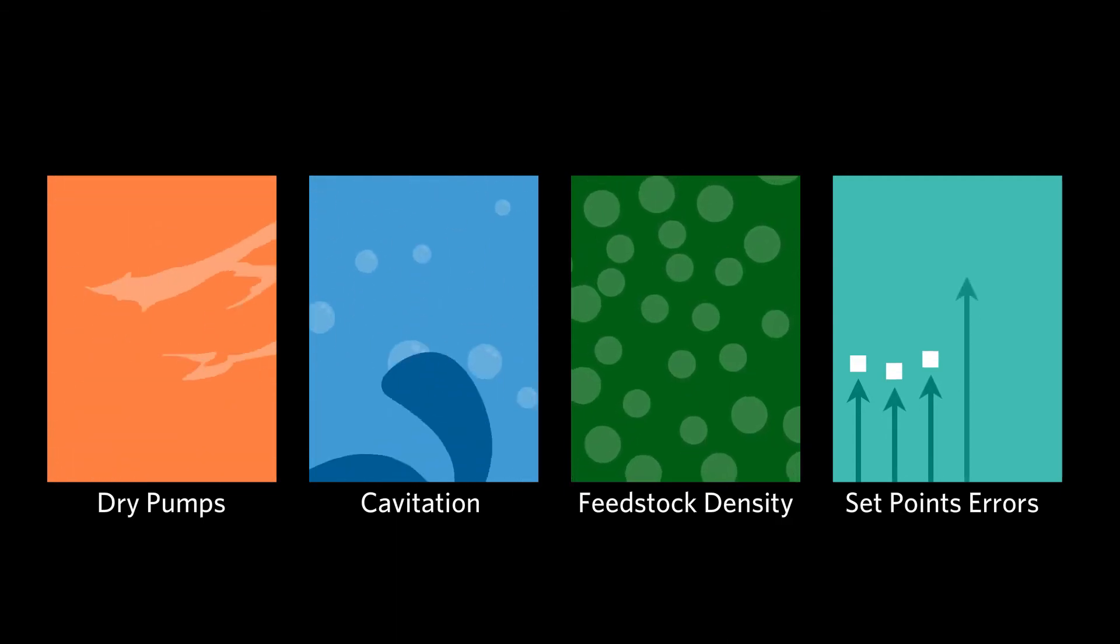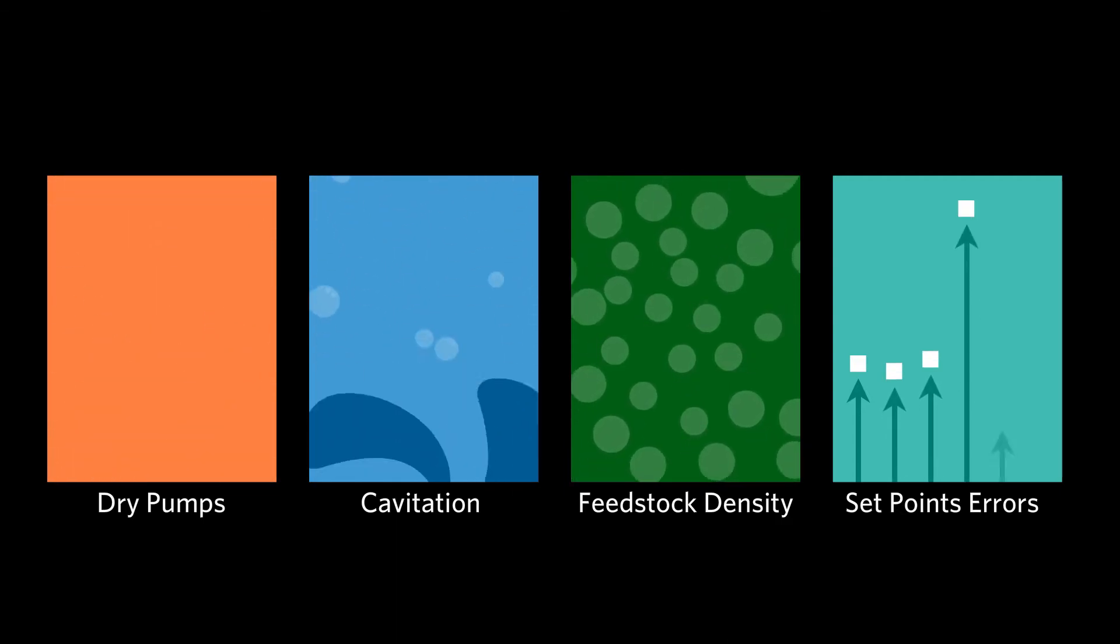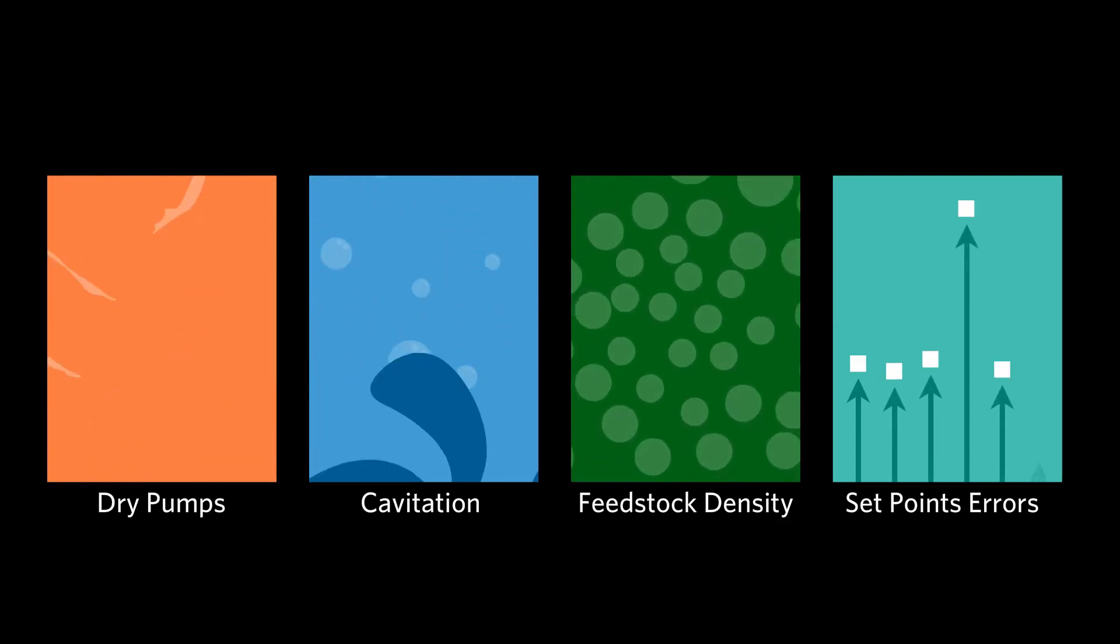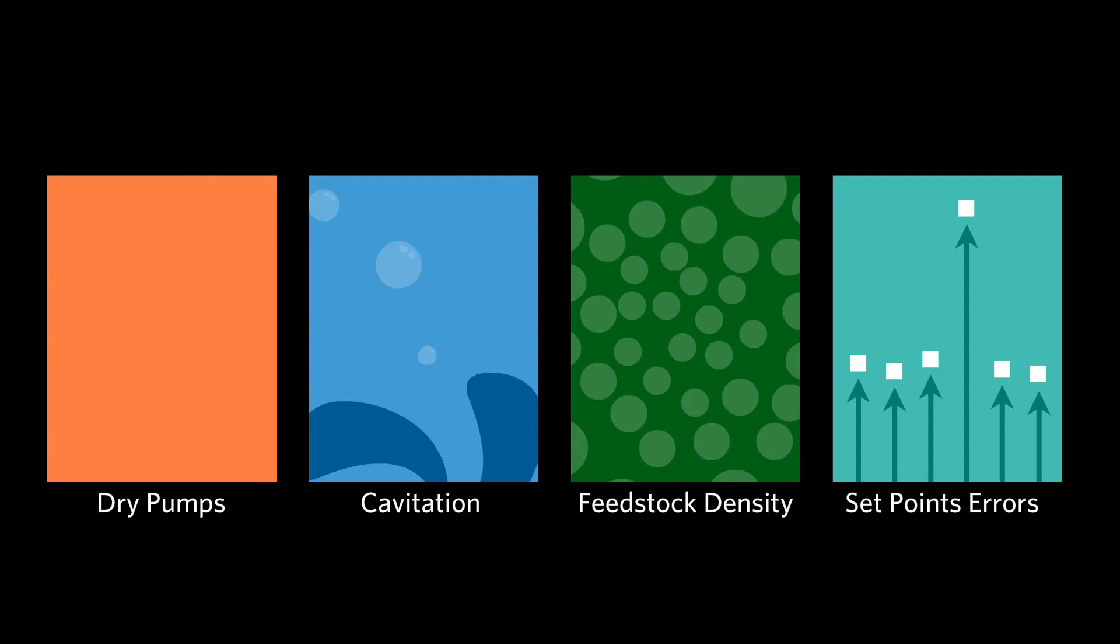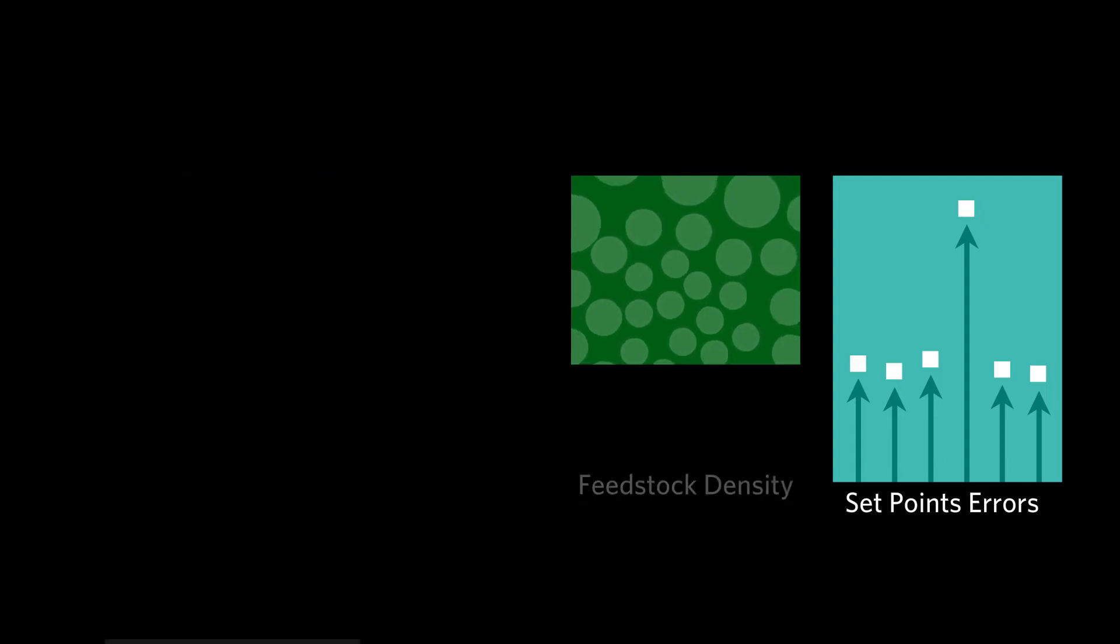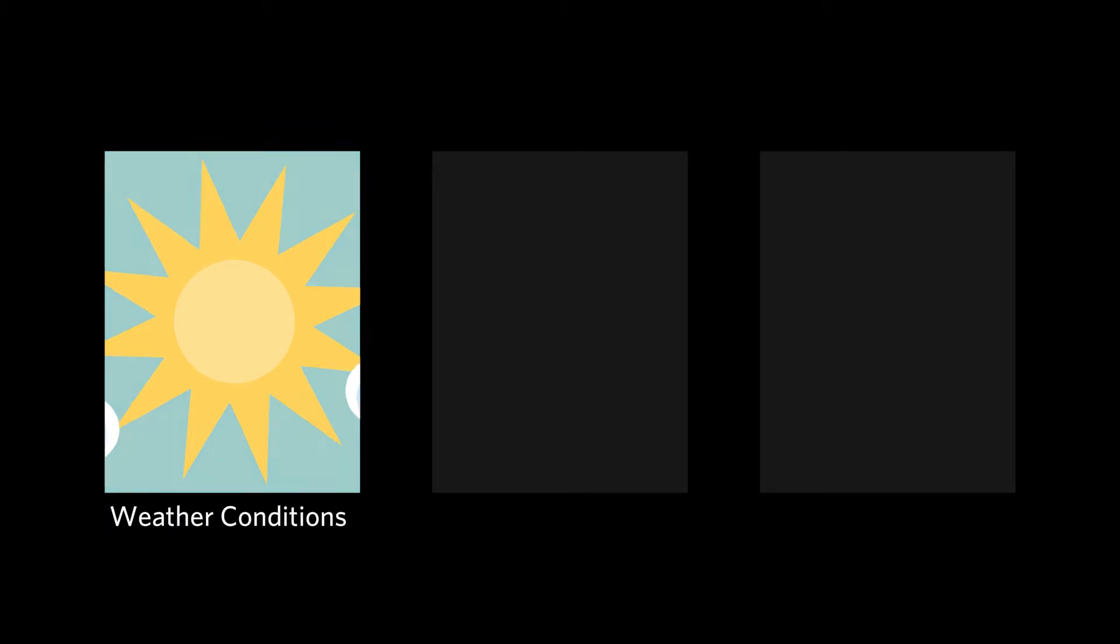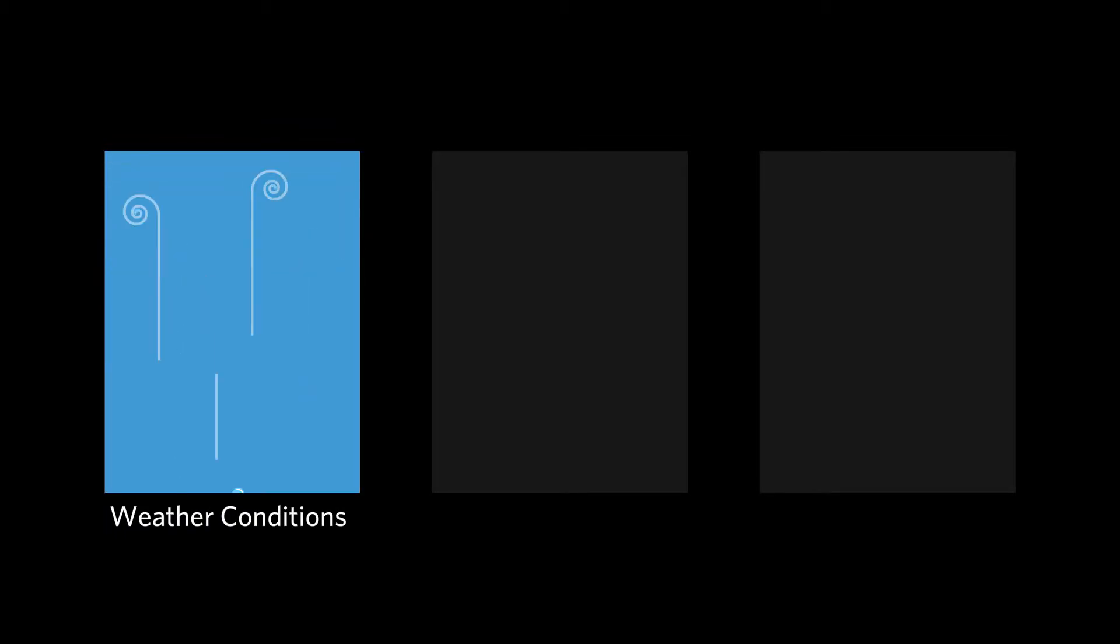However, agents have detected severe liquid carryover conditions into compressors resulting from inadequate cooling due to warmer weather conditions that increases gas velocity in the separator, shearing micro droplets from the surface into the gas stream.